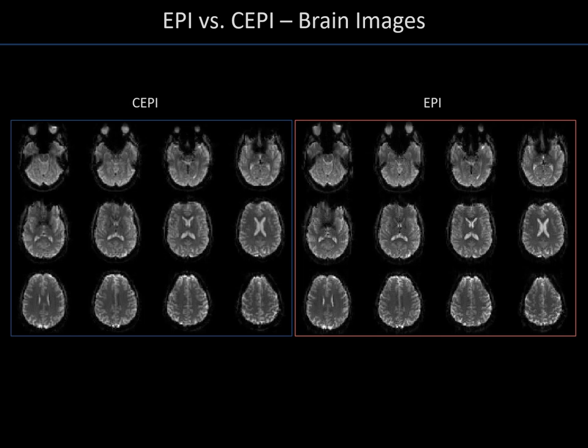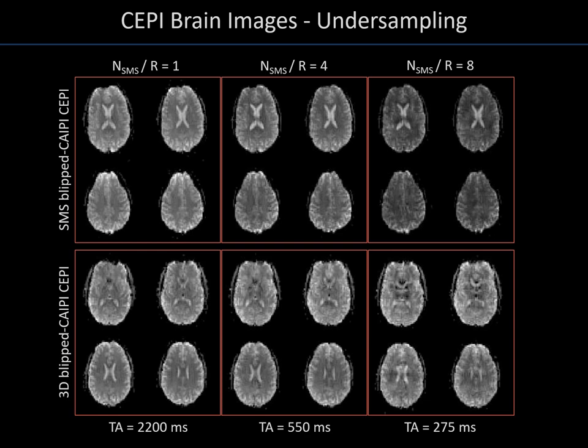These are the fully sampled brain images obtained using the CEPI and EPI trajectories. Thirty-two slices of three millimeter thickness were obtained. In agreement with the results from the simulations, the image quality is very comparable. The acquisition time for fully sampled images is 2.2 seconds. To accelerate the acquisition, blipped-CAIPI undersampling schemes were applied with four- and eight-fold acceleration. Using these CEPI gradients, SMS as well as 3D volumetric CEPI fMRI time series were measured. Each set of images was windowed equally, and one can see that in the case of SMS, a clear reduction of the SNR occurs with higher multiband factors, while for the 3D acquisition the SNR is nearly constant.